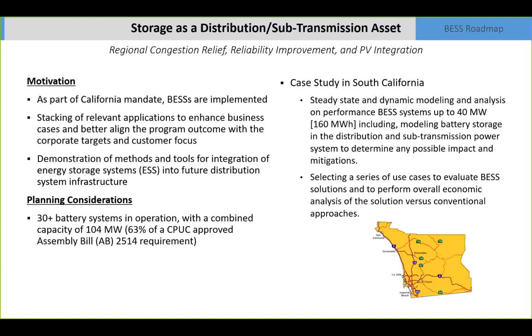What was interesting was how it was used in the market for stacked applications when it wasn't needed for capacity deferral. But coming back to the need to do the homework in the state - an outgrowth of the original California mandate was that utilities were basically told each to put in 120 megawatts of storage the next year as part of that mandate. Speaking with utility engineers, the critical dimension for them was where they could site it - to get it in within a year, they had to find a non-remediated environmental site that they owned and that was convenient to a substation. So the economic and engineering analysis took a back seat to just finding where they could get it in on time for the mandate. I bring that up again to say: do the homework first.